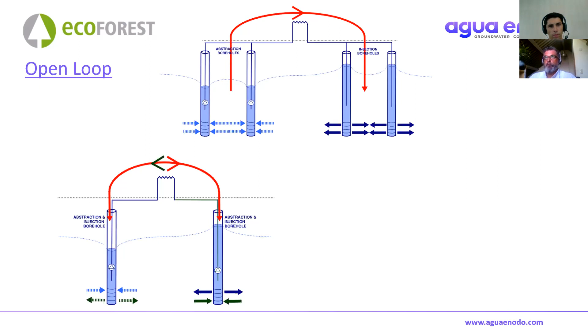The idea, even though it's a slightly more complicated and expensive setup, is that we try to take advantage of creating a warmer and a colder bubble around those dedicated wells. With a pump-and-dump or unidirectional system, we want that flow of warmer or colder water to move away from the abstraction borehole, so we're not pulling it back. But with a reversible system, we're hoping to take advantage of that and gain some extra efficiency.